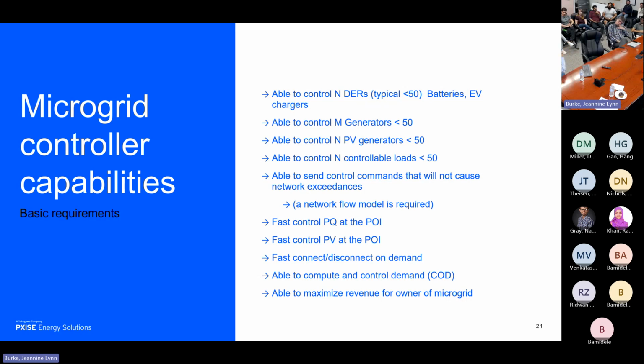Why don't I put a simple PID controller on the angle of the main grid and a set point of 0? I want those two angles to be equal, and I put it in a fast feedback loop that drives the frequency signal of the inverter until I get the frequency that I'm within 10 degrees, and then the system will close. The relay will close, bam. So that's an angle tracking feature.